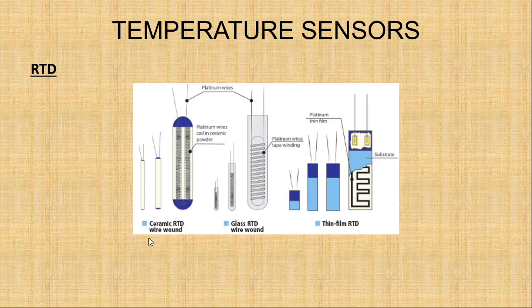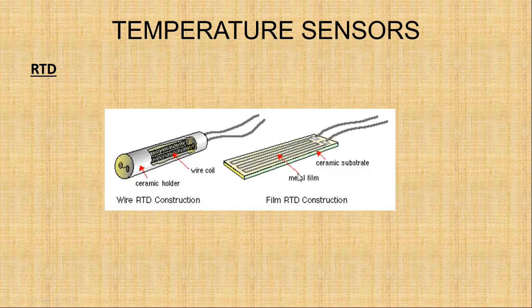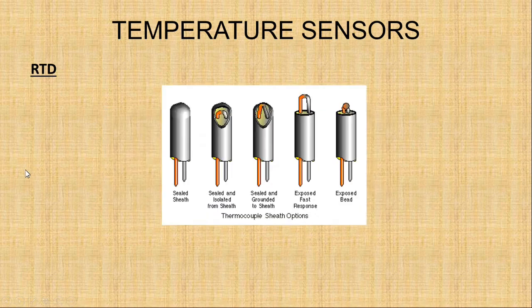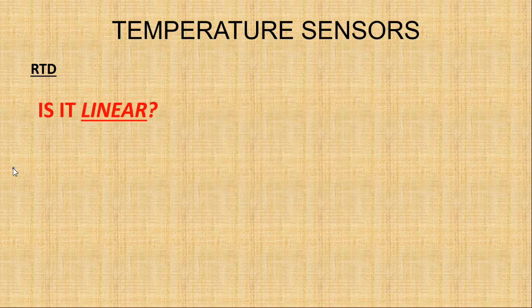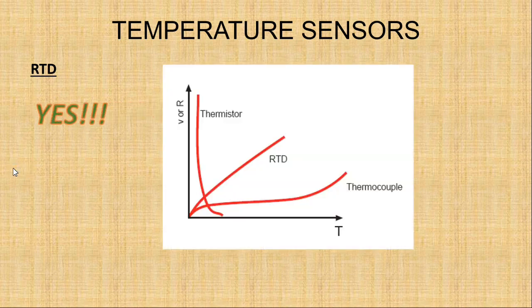Here's the diagram showing the various ways in which they're constructed. Some are flat. I have never seen a flat thermocouple or a thermistor, which we'll get to in a minute, but I have seen flat RTDs. Again, showing the flat versus the round, and another diagram showing how the tip is sealed in various methods. So is the RTD linear? Yes. Here is an RTD diagram. It's showing the comparison between the thermocouple, which we've spoken of, and a thermistor. The RTD, for all intents and purposes, is the most linear temperature sensor. It might need some correction, but not much.